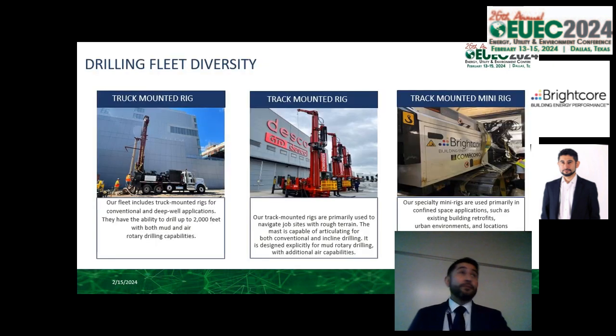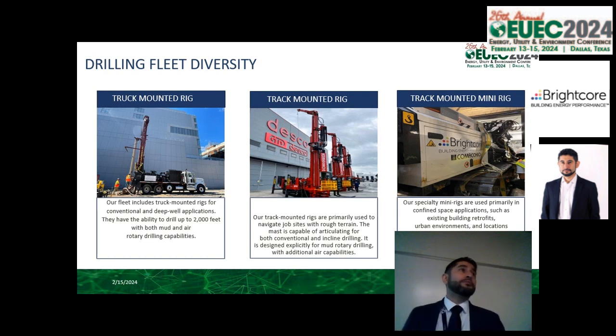At Brightcore, for example, we've got fleet diversity. You have crossover with water well drillers on truck-mounted rigs, or coring rigs like typical Copco or Boart Longyear rigs, then track-mounted production-style rigs. The typical ground source heat pump depth for these boreholes is about 500 feet, depending on legislation—and I say that because Brightcore is based in New York. We're proudly the last company on record to apply for a mining permit to do geothermal. Right after the governor signed off, we had spudded a week prior, then the law changed, and that was it. But you can now go to depths of about 850 feet.